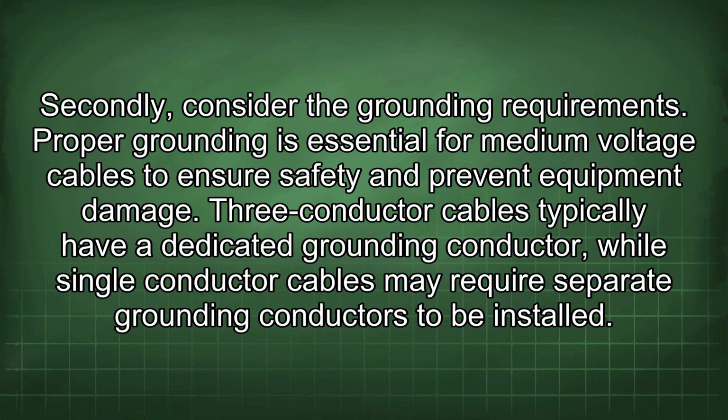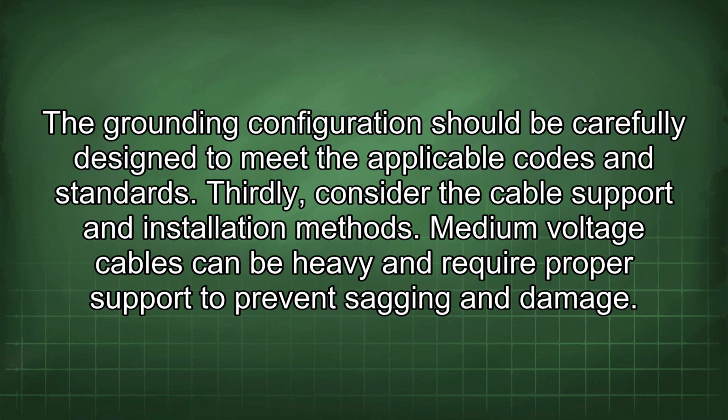Secondly, consider the grounding requirements. Proper grounding is essential for medium voltage cables to ensure safety and prevent equipment damage. Three-conductor cables typically have a dedicated grounding conductor, while single-conductor cables may require separate grounding conductors to be installed. The grounding configuration should be carefully designed to meet the applicable codes and standards.